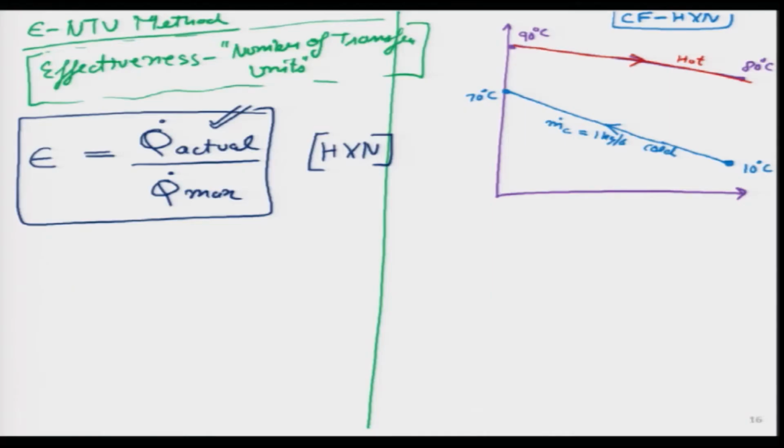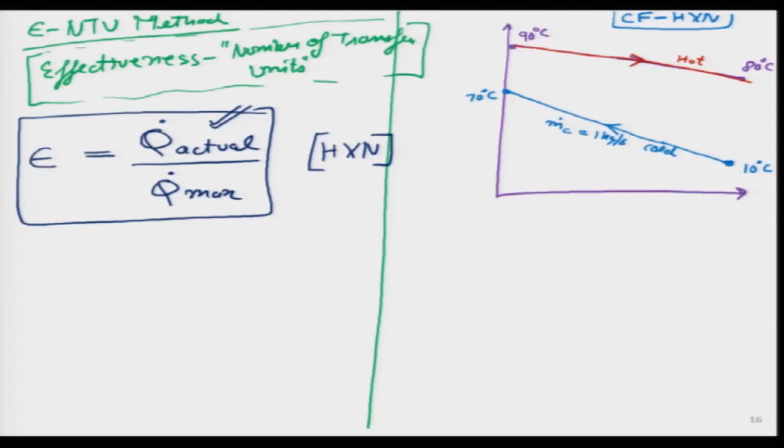The direction I am going to move is to close the valve a little bit, which means I am forcing less mass flow rate through the cold side. In other words, I want to make this 1 kg per second a little bit less, let us say 0.9 kg per second. Let us see what will happen then. If I go back to the slide, this was my original case, which I will call case 1. In the second case, I make it 0.9 kg per second.